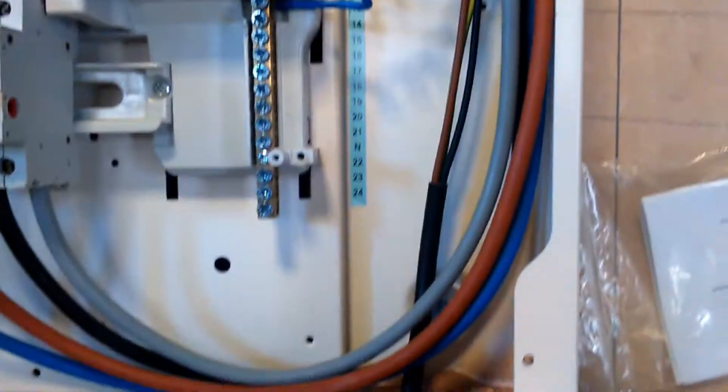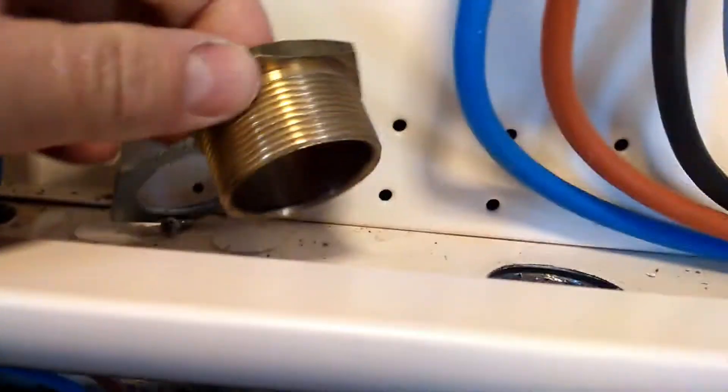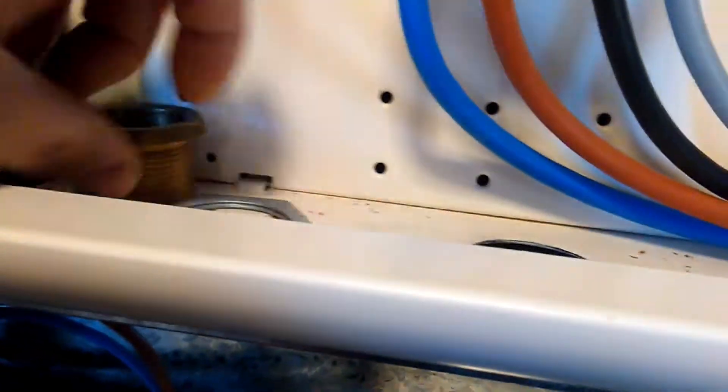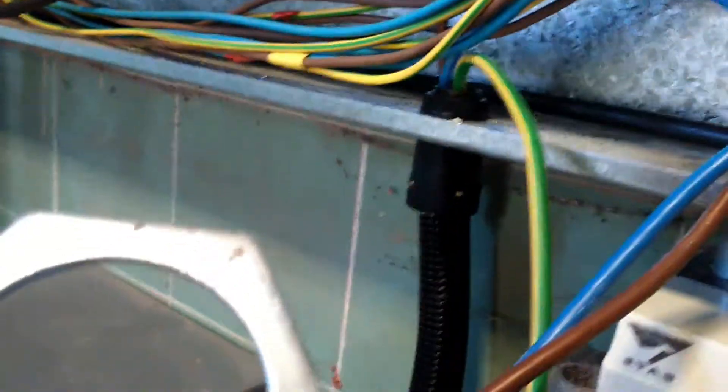Understandably, we can't move the fuse board up an eighth of an inch. I've had to take this bush out because it was just a bush like that, loose in the hole with no lock nut. So I'm going to put the lock nut on and then we feed this cable back into the fuse board.